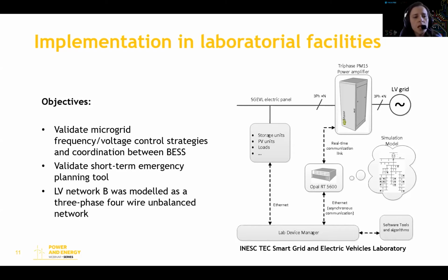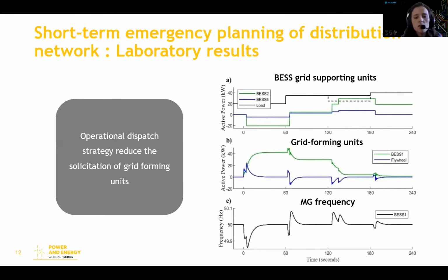So we wanted, as I said, in the first place to validate all the local control strategies for voltage and frequency regulation, and then also test the results and the impact of the dispatch strategy on the stability of the microgrid. So we did it, and you see here the results. We have on the bottom the microgrid frequency, and you can see the first transient is related to the islanding transient, and the smaller ones are related to the dispatch of the battery energy storage system grid supporting units.